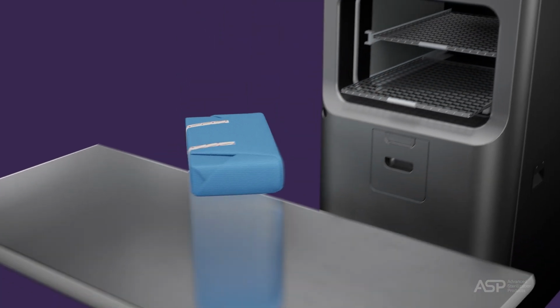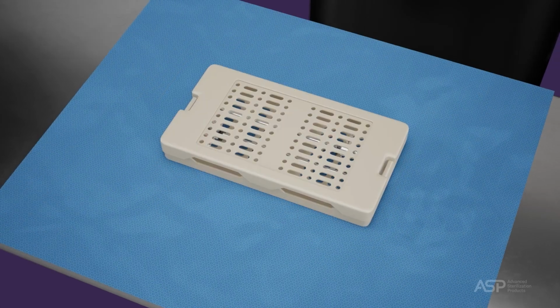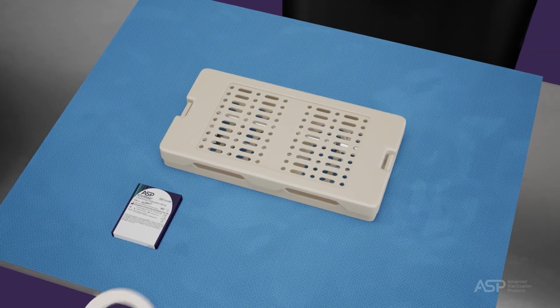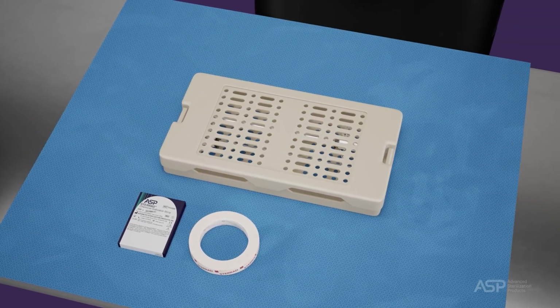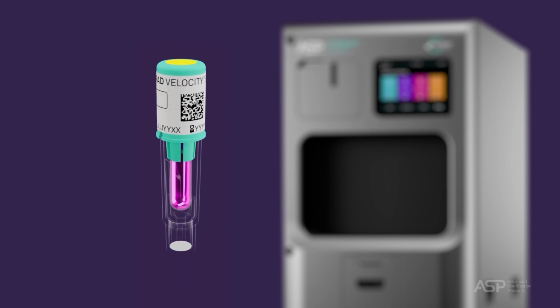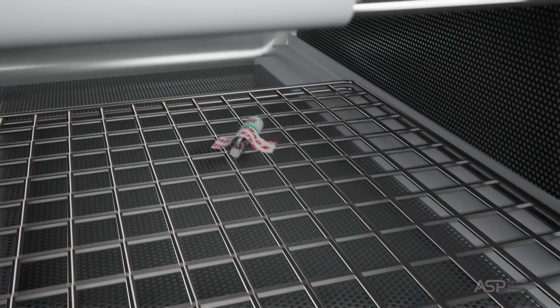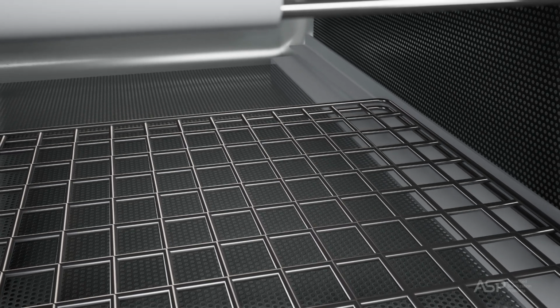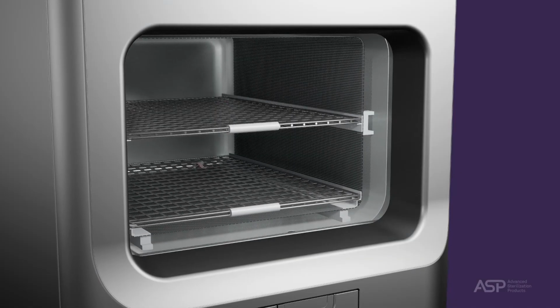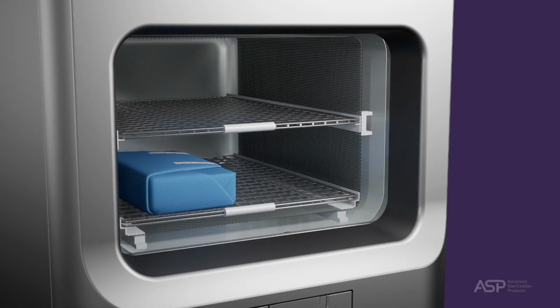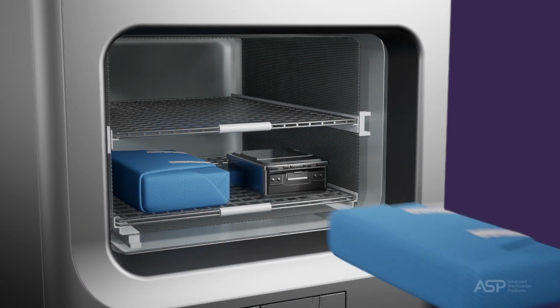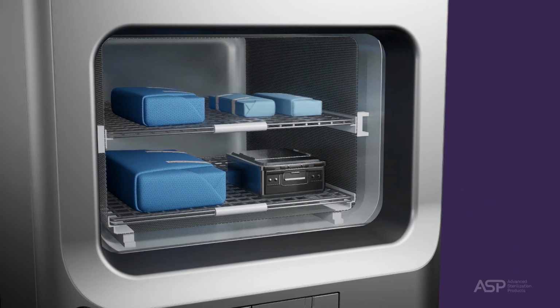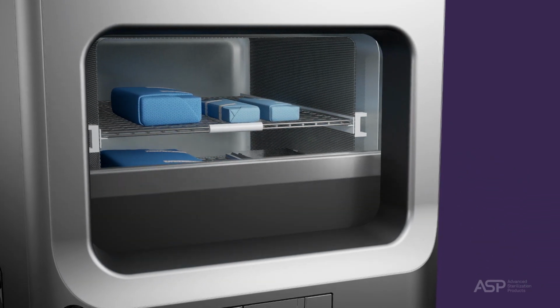Loads from canceled cycles should be rewrapped using new packaging materials, STERRAD chemical indicator strips, and SealSure chemical indicator tape. If a biological indicator was used in the canceled load, the previously used biological indicator must be disposed of per your hospital or healthcare facility's policy, and a new biological indicator must be placed in the chamber before restarting. To maintain the highest patient safety, ASP recommends monitoring each sterilization cycle with a STERRAD Velocity Biological Indicator (BI/Process Challenge Device (PCD).